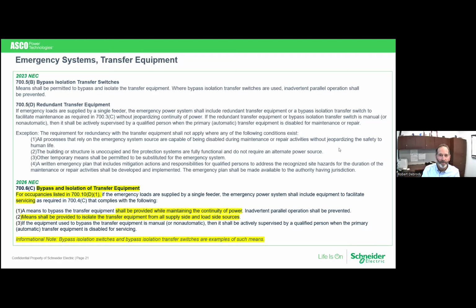They don't want that to happen. They want to make sure that there's a continuity of power between the two when you switch from one to the other. And number 2, it's a new paragraph, but it really means just make sure that when you isolate that transfer switch, you can completely isolate it from everything and actually pull it out and repair it and maintain it, whatever you have to do.